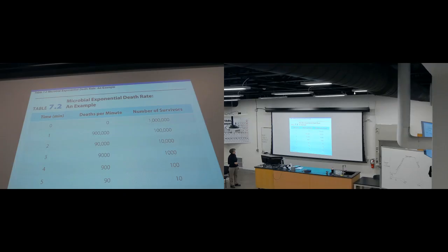So what it means, let's say that at minute 6 you had 100 microbes, you have to go at least 3 more minutes, at least, to sterilize this instrument. So instead of 6, you will have to have at least 9 minutes, but what the heck, a minute can actually save a life.